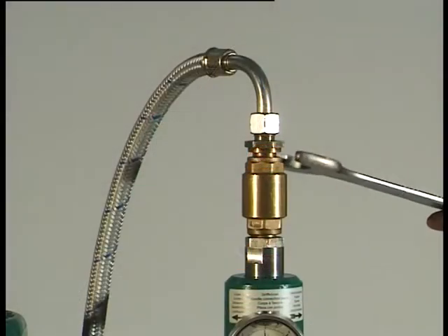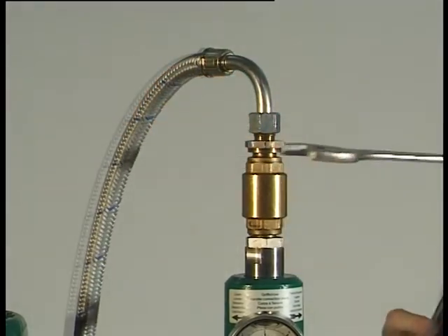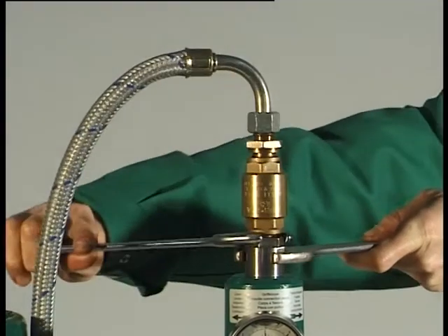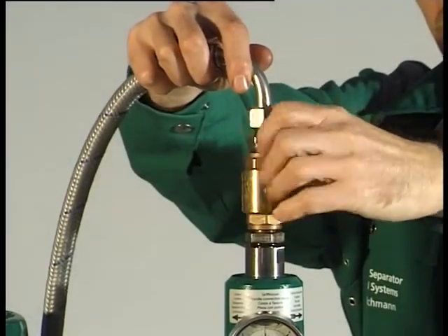Attention: do not loosen any part of the separator before the bowl comes to a standstill. Use only genuine spare parts from Westfalia separator. Unscrew the union, non-return valve and double nipple together — right-hand thread.